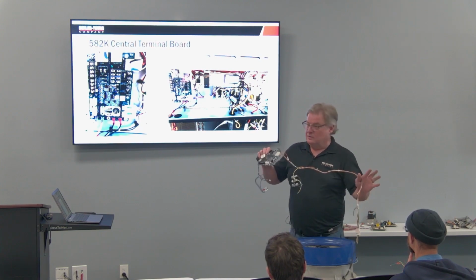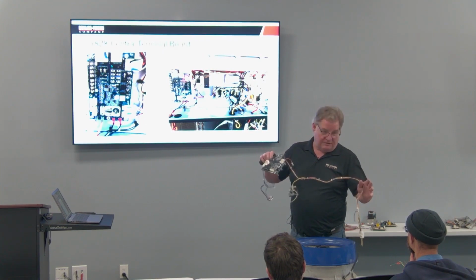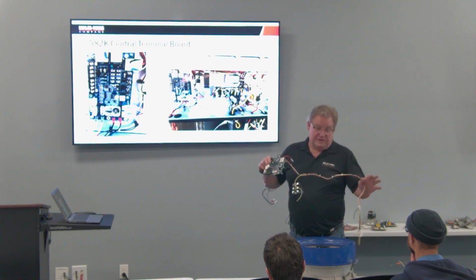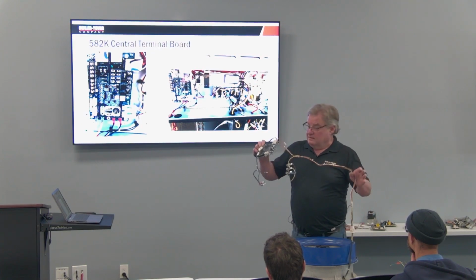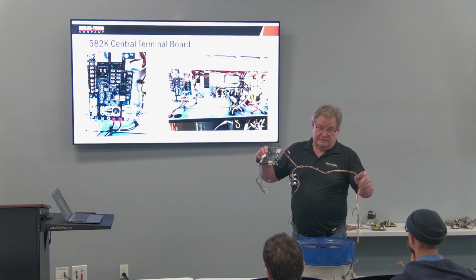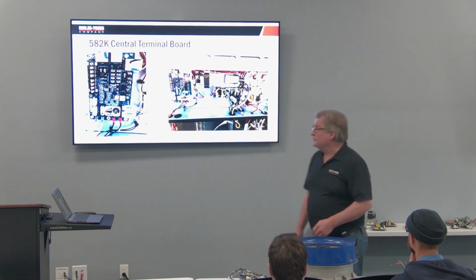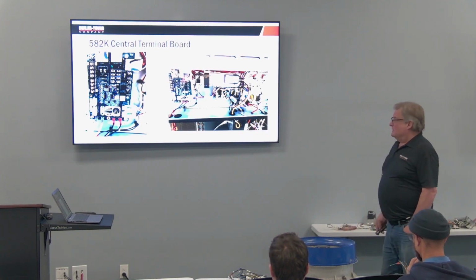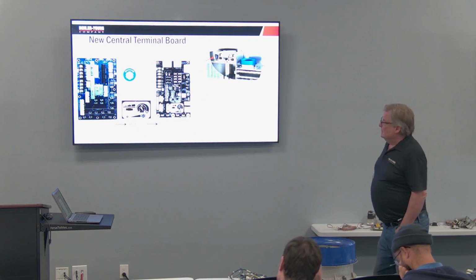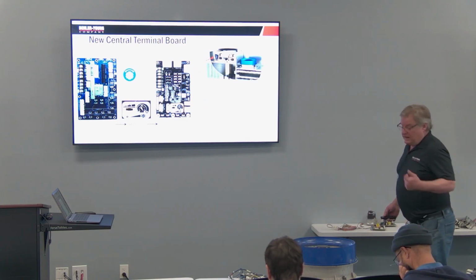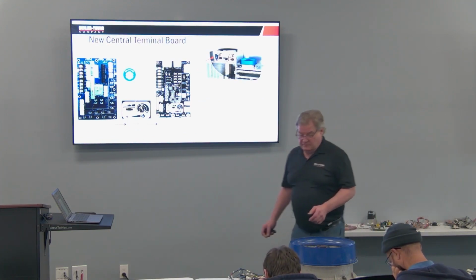Okay, and this is where we lose these motors, because when we have a power surge, we have high voltage, we have low voltage, we have brownouts. There's nothing protecting that motor, all right? So there's power on it 24 hours a day, because we no longer have a contactor for it. All right, so what else is different about that board?